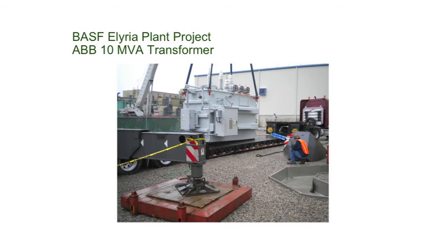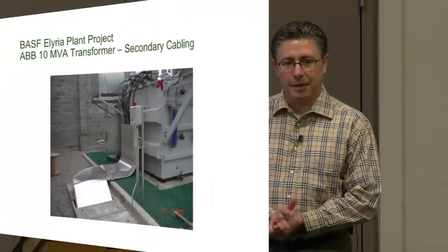You can see in the foreground the secondary bushings. We used a Pfisterer bushing as a BASF spec. That's a German product instead of a standard cable bushing. And also on this transformer we have a Reinhausen tap changer that's in tank. It's the first one South Boston built. Again, it's a European design, but we were able to implement it on this project out of our South Boston facility.